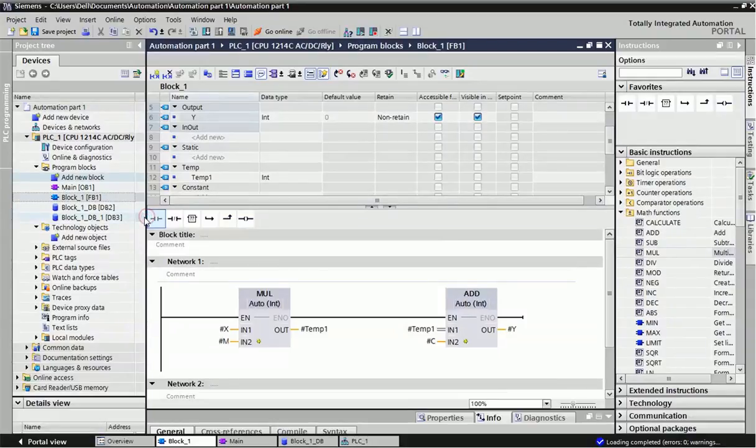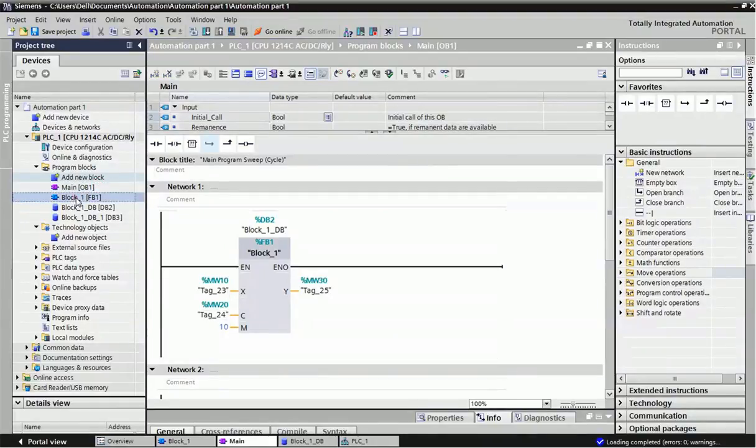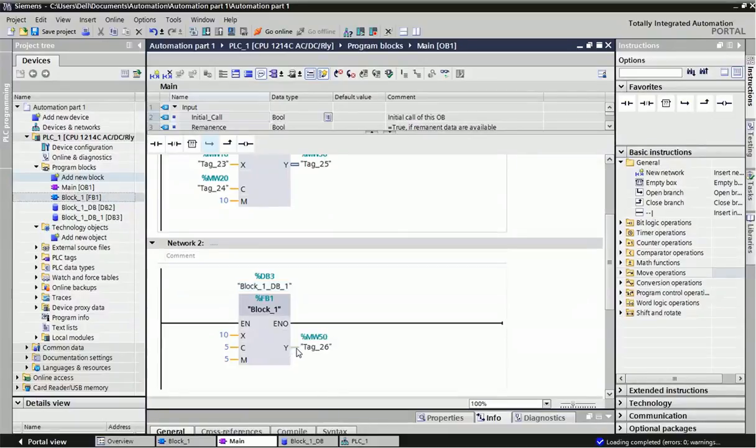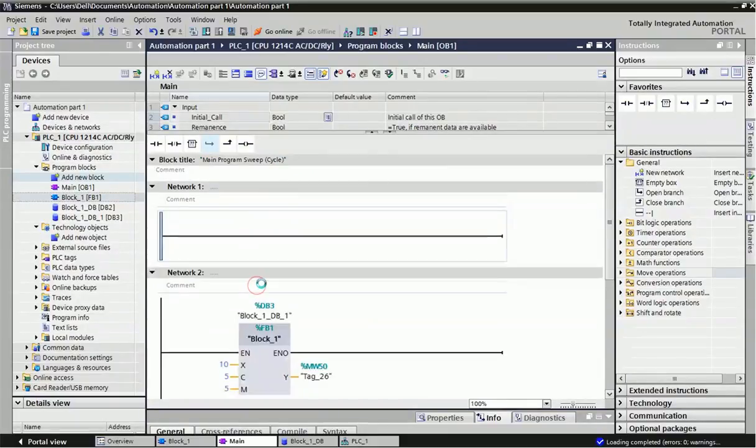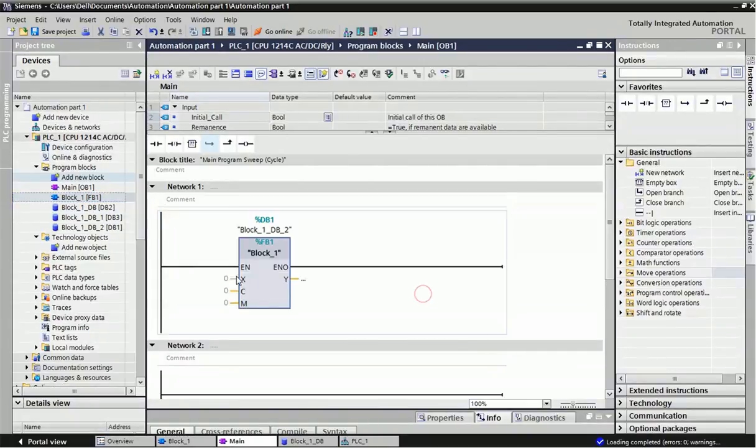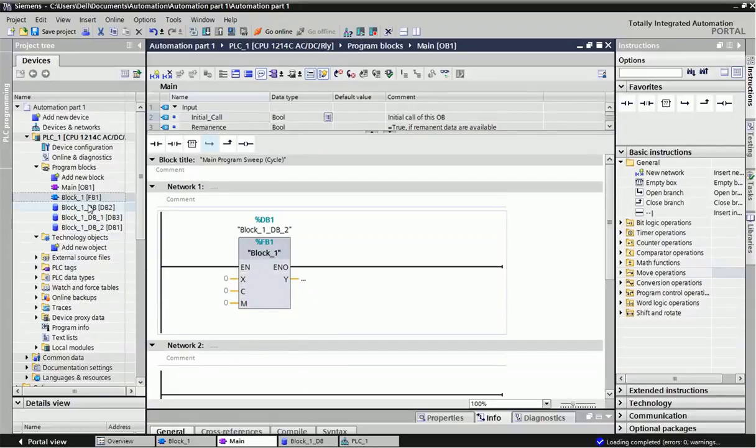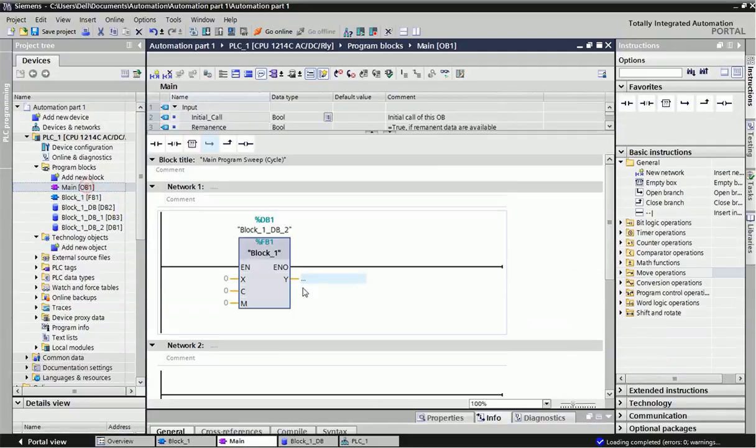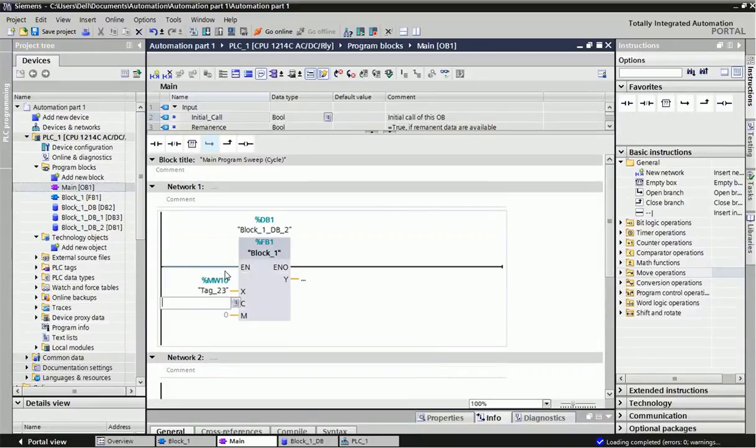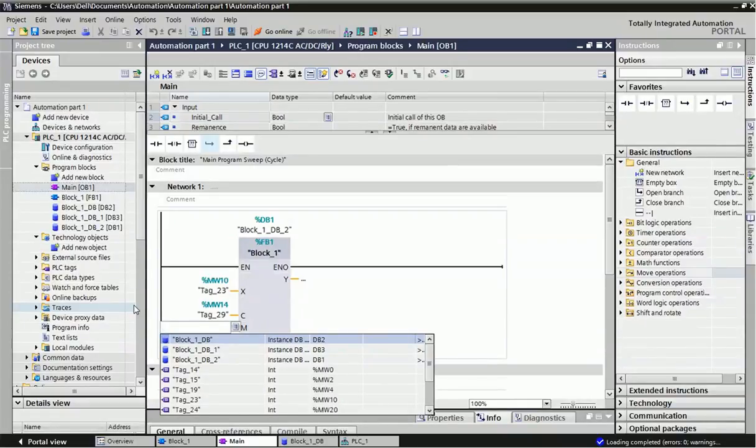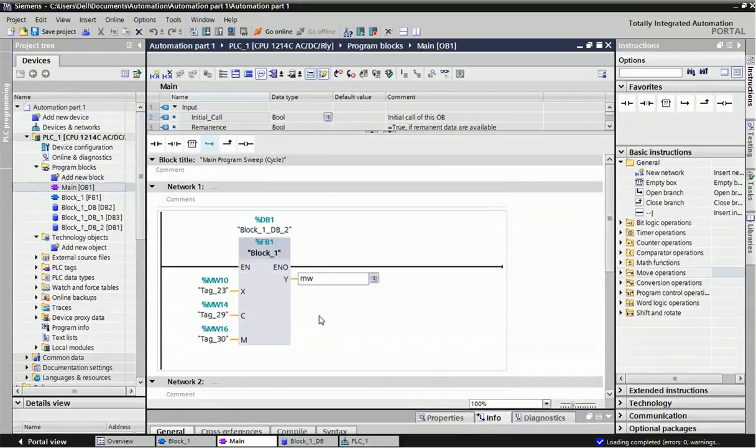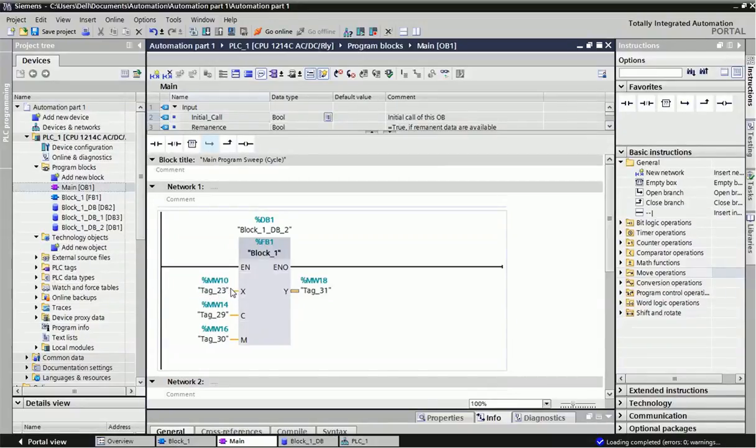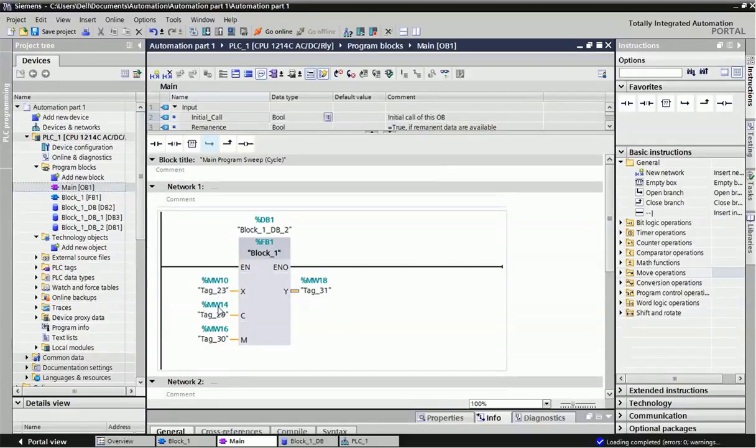Now I'll use this function block in the main OB. In main OB I've called this function block with drag and drop. I've used it two times. You can just drag and drop like this. This total equation becomes one block in main OB. Now you can directly assign addressing here. I'm assigning addressing from memory word, so we can give different values. We're giving memory word addressing with two-value increments because this word consists of 16-bit resolution, so it won't overlap. It takes this addressing by skipping two values.